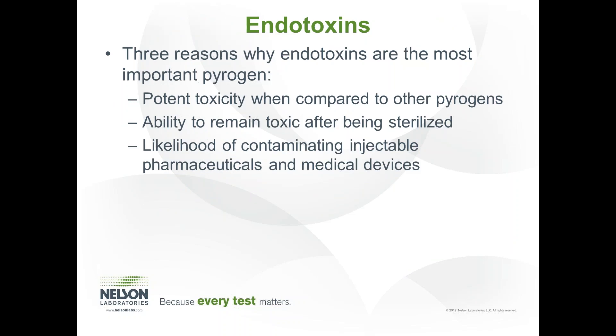The three reasons that endotoxin is the most important are its potent toxicity when compared to other pyrogens. The next most potent pyrogen is the peptidoglycan from gram-positive bacteria, and it is something along the lines of 50,000 times less pyrogenic than endotoxin. Endotoxin is also a very stable molecule. It can resist almost all sterilization methods such as ethylene oxide or radiation. Typically, in order to remove endotoxin, it needs to be depyrogenated.